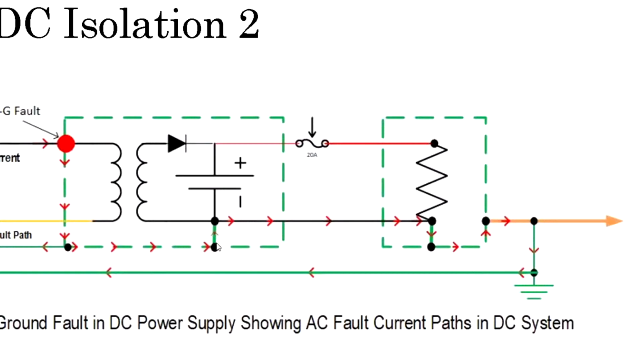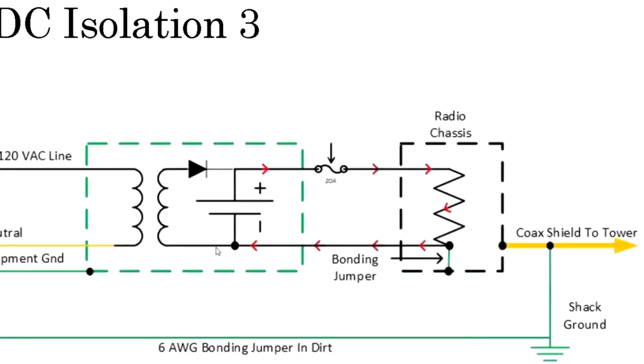There's no reason to have that, and all we got to do is isolate the two systems. So this is where you hear you want to be isolated from the AC systems is exactly correct, but they must have a common path. So how do we do it? Okay, again, the same circuit, except now we've made a modification. We can't get inside your radio and get this bonding jumper out, okay? That's just impossible. But we can fix your DC power supply.